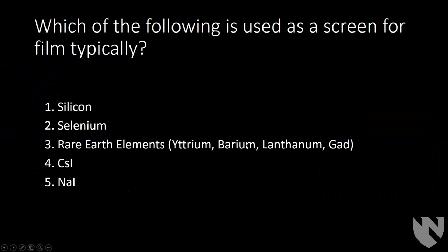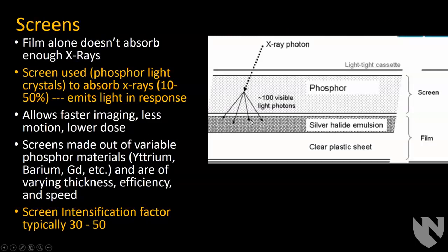First question: which material is used for screen film as a scintillator? Rare earth elements are typically used for the scintillators. The film by itself won't absorb enough x-rays — it's very thin and not efficient at converting x-ray energy into silver particles. X-ray photons converted into light are much more efficient at creating the image, so you don't need as much dose. The screens are made out of various materials, usually rare earth elements, varying in thickness, efficiency, and speed. The intensification factor of a screen is typically 30 to 50.